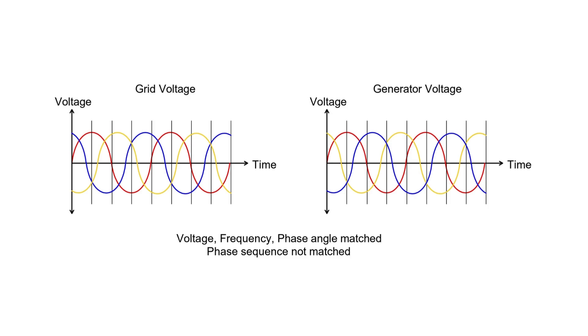Now, about the phase sequence, how do you check it? The phase sequence is usually checked only at the beginning when the generator is first connected to the grid. After that, you only need to turn the breaker on and off without worrying about the phase sequence repeatedly.